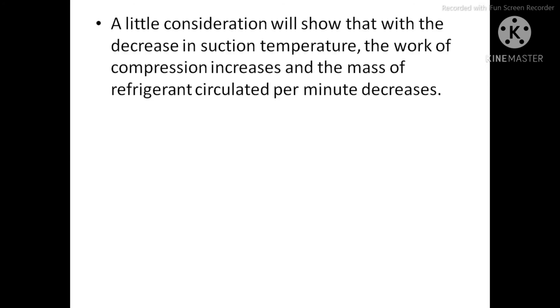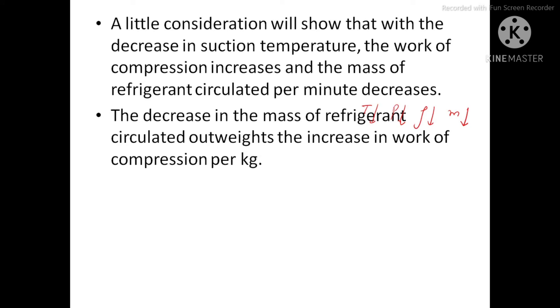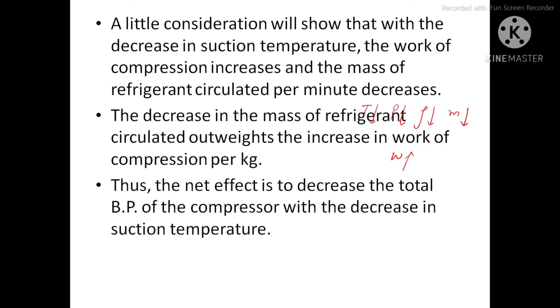When suction temperature decreases, the work of compression increases but the mass of refrigerant circulated per minute decreases, because the pressure decreases and the vapor density also decreases. The decrease in mass of refrigerant circulated outweighs the increase in work of compression per kilogram. Thus the net effect is a decrease in total brake power of the compressor with a decrease in suction temperature.